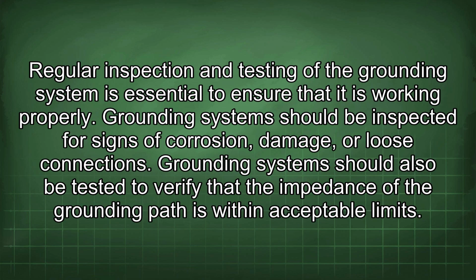Regular inspection and testing of the grounding system is essential to ensure that it is working properly. Grounding systems should be inspected for signs of corrosion, damage, or loose connections. Grounding systems should also be tested to verify that the impedance of the grounding path is within acceptable limits.